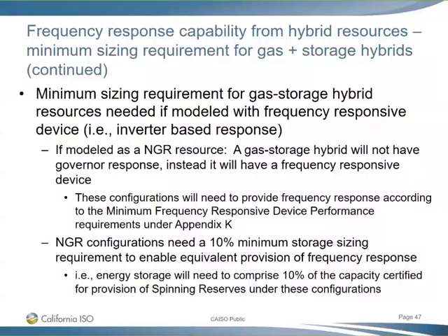The ramp rate is already considered within the rest of the Appendix K requirements and your criteria, as far as your maximum output in 10 minutes time. When you look at the totality of all the criteria, your ramp rate would have to be considered in order to account for that amount of spinning reserve. But for frequency response, it was just appropriate to spell out that there are two different varieties, whether you're coming in as a gas resource or an NGR. They're going to be different, so depending on how you bring your resource in, you want to plan appropriately, because you're going to have two different droop responses, essentially.